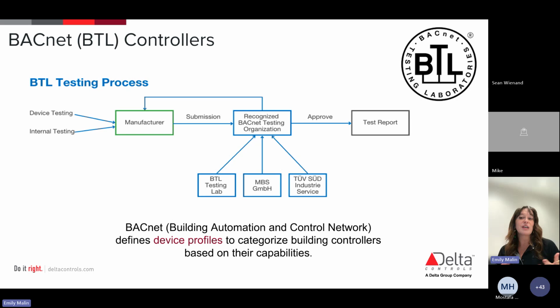So this is a specific number, it's a minimum number that the device must support, and it defines what those capabilities are. And it also defines the interoperable capabilities between each of these device profiles. We'll talk a little bit about BIBBs in a minute, but just know that this is actually what they are using to create these device profiles. And then once they go through all this testing, they get approved, and you do get the certificate.